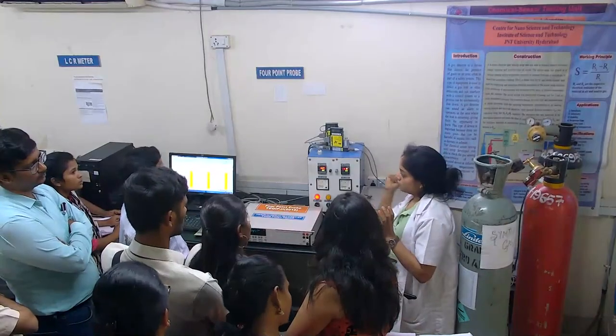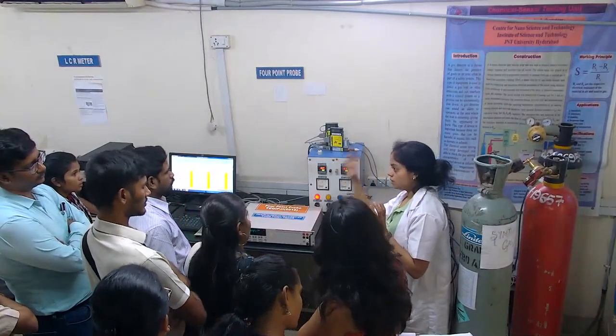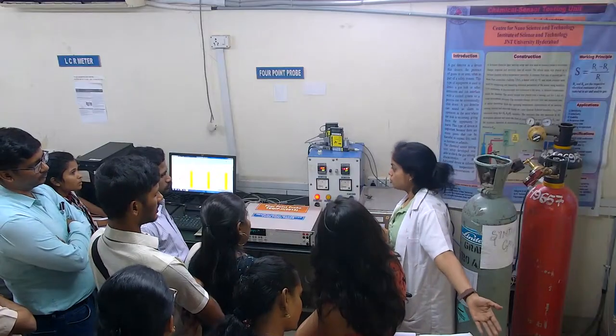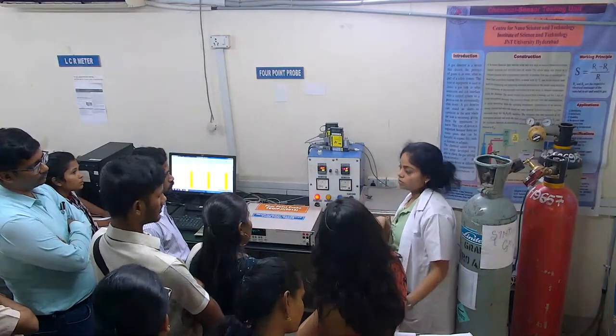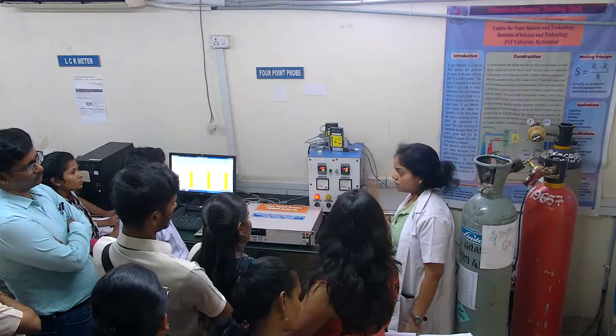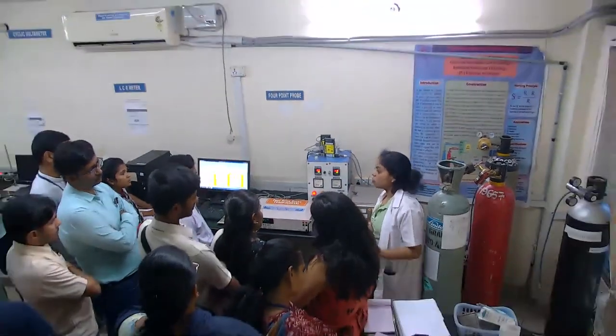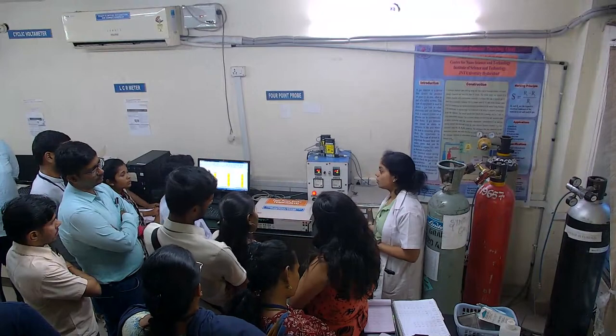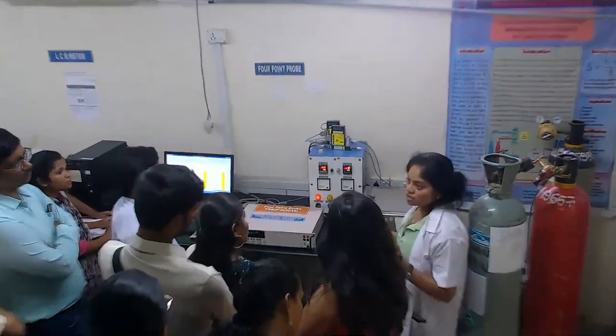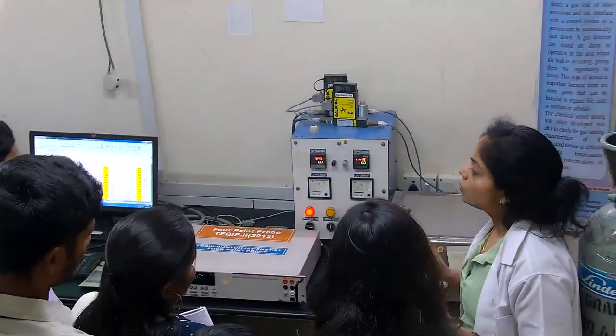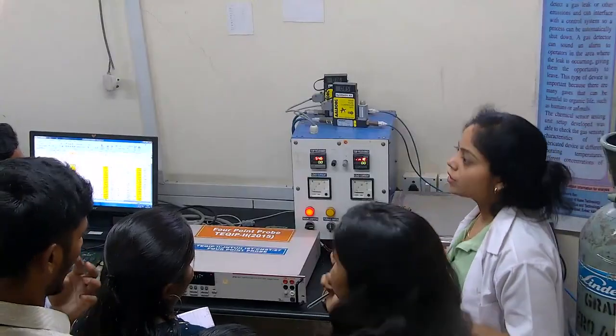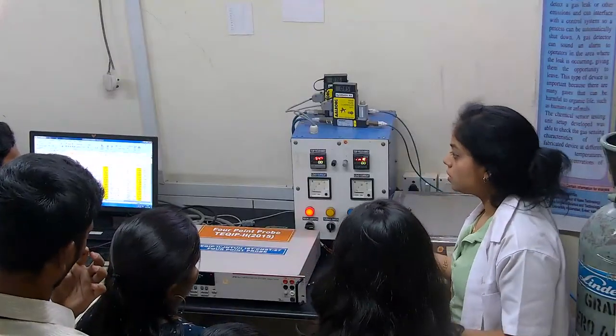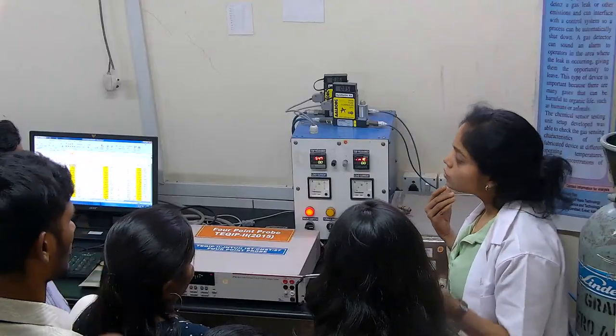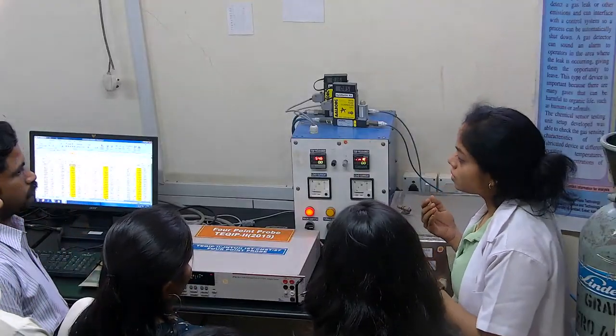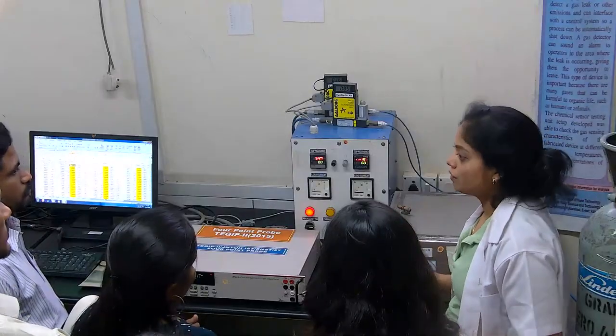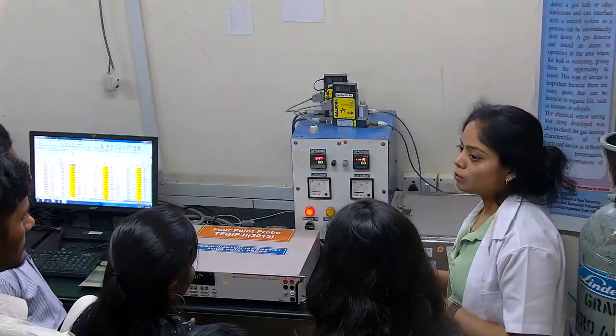That means 85 should be your synthetic air, 15 ppm should be your isopropanol. Test is done with isopropanol. Again, 85 should be with your synthetic air, 15 should be with some acetone. Whatever we ask for. Usually people do isopropanol, acetone, methanol, ethanol. These are all called interference studies. So that is how you will get interference studies. Say if you have satisfied him by showing 6 gases: Sir, I am able to give you the data using 6 interference studies, and out of the 6, my material is doing good, then he'll say, okay, fine. So that is how you'll be able to give the data.